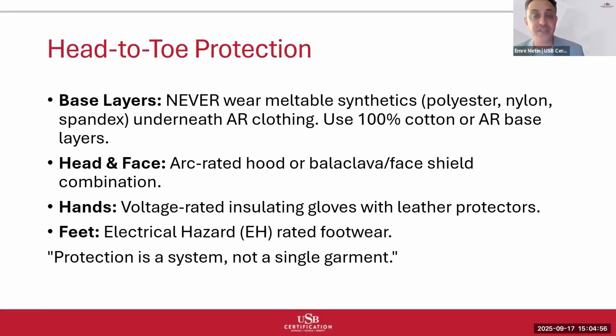Hands. Voltage-rated insulating gloves with leather protectors. This requires a system approach combining electrical protection and thermal protection. Voltage-rated insulating gloves protect against electrical shock, while leather protectors provide arc flash protection and mechanical protection for the insulating gloves. Different voltage ratings require different glove thicknesses and testing requirements. The combination must be appropriate for both the electrical hazard and the arc flash incident energy levels.